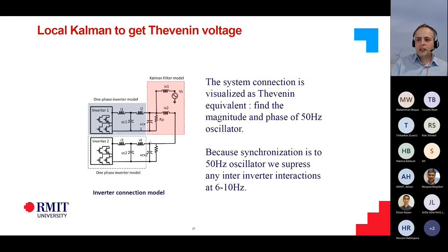At the same time, we tried to create a good reference point for the inverters by using the Kalman filter. So instead of the inverters relying on their terminal voltage, we would create a reference point for these inverters based on measurements across different parts of the network, and those measurements would then be fed into the different inverters in the network.